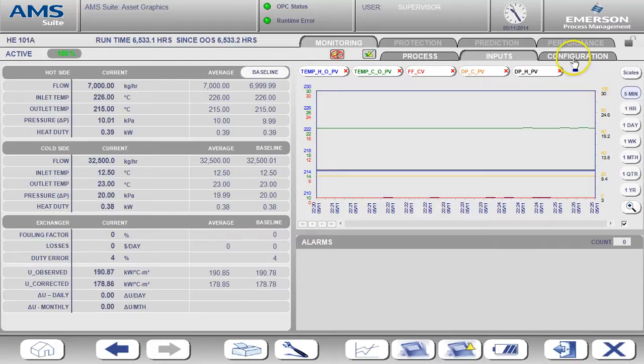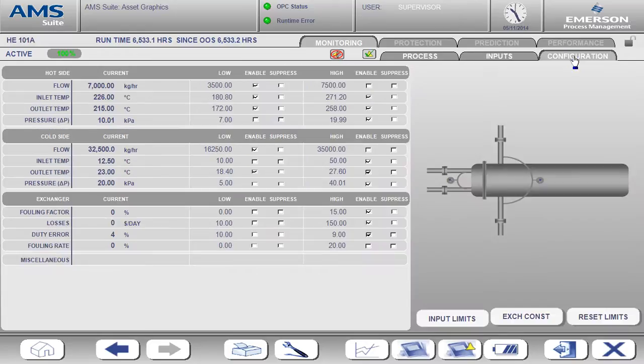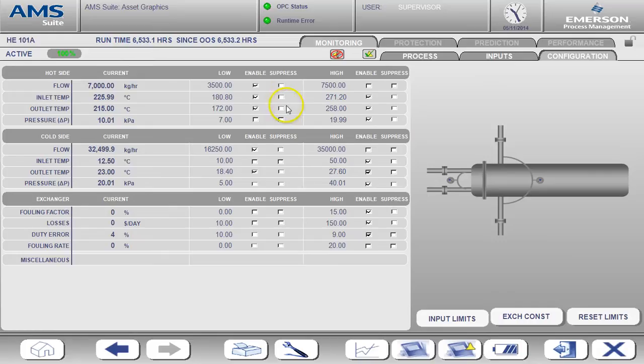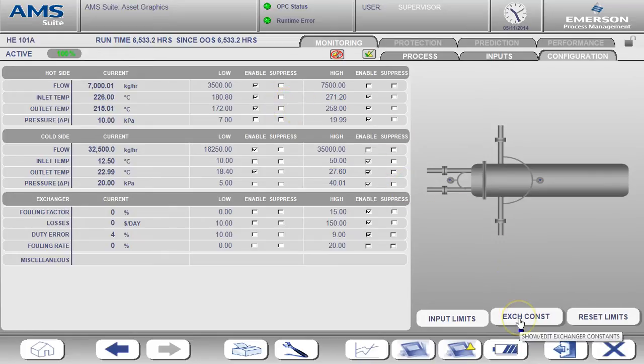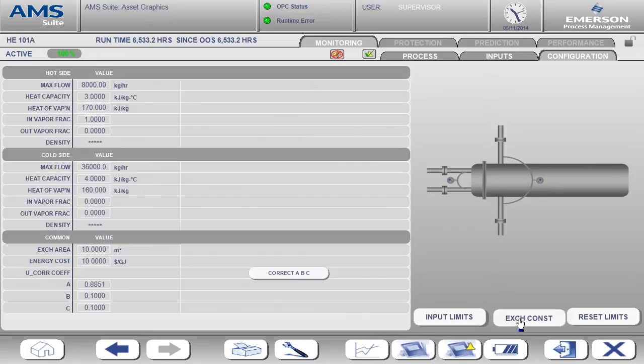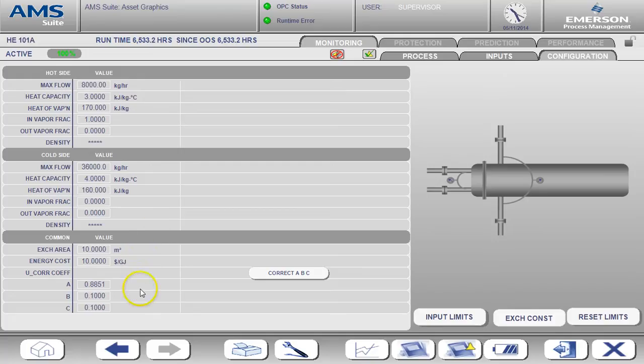I am now moving over to the configuration tab. From here you can configure the alarms. This is also where you will find the exchanger constants entry page. The exchanger constants such as heat exchanger area and heat capacities are important so that the calculations are specific to this particular heat exchanger.